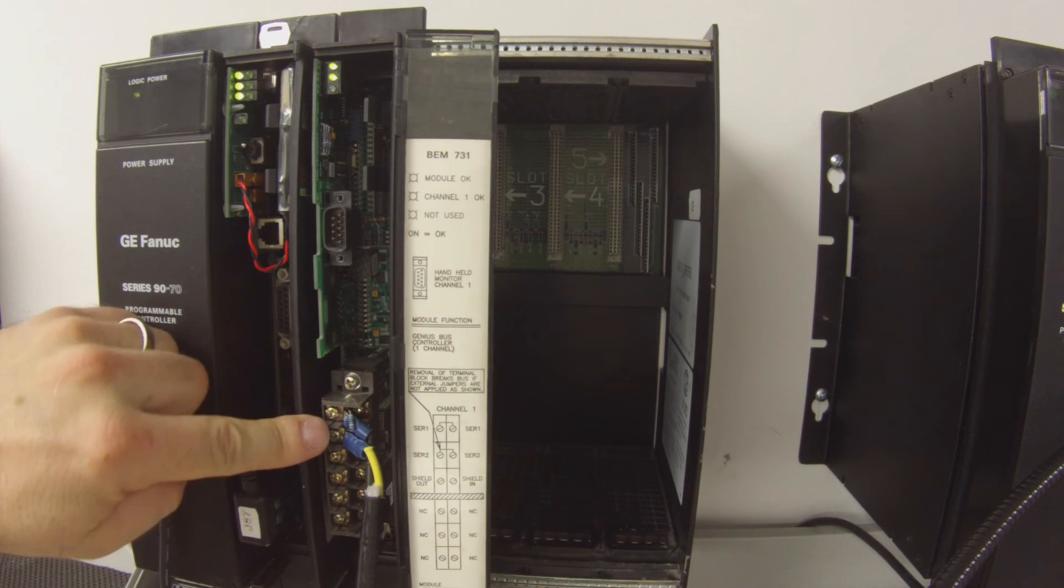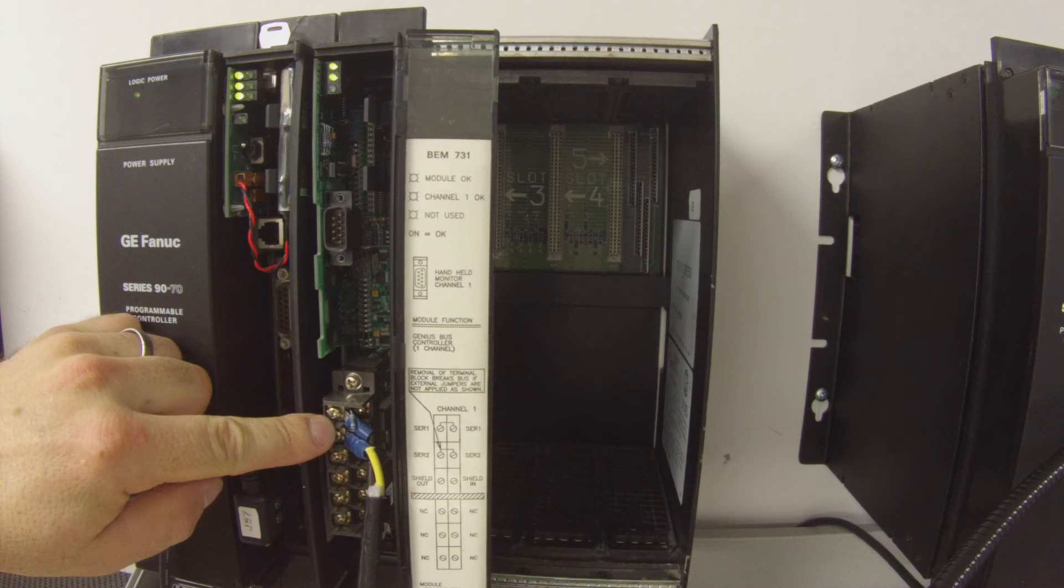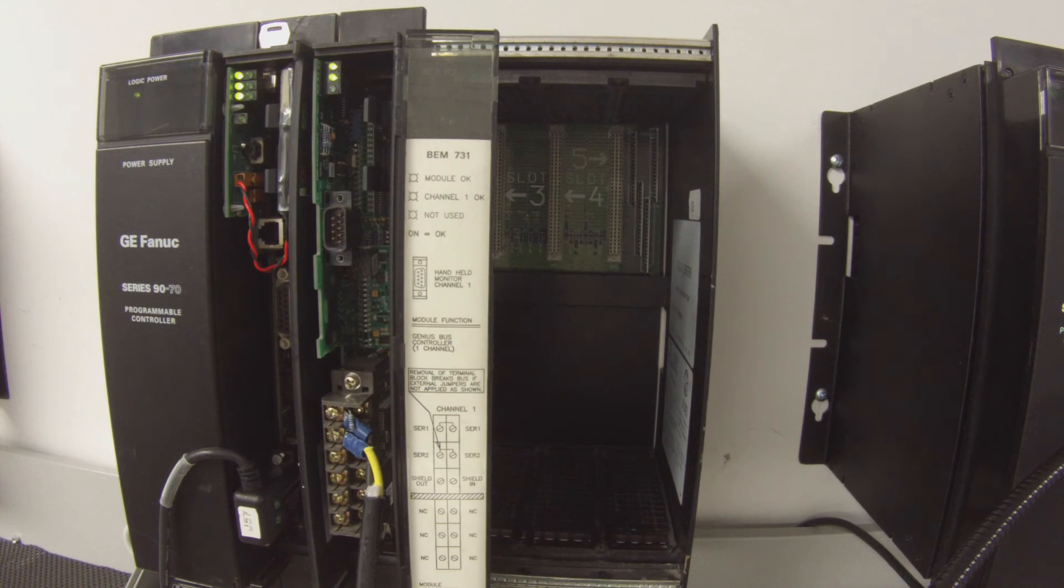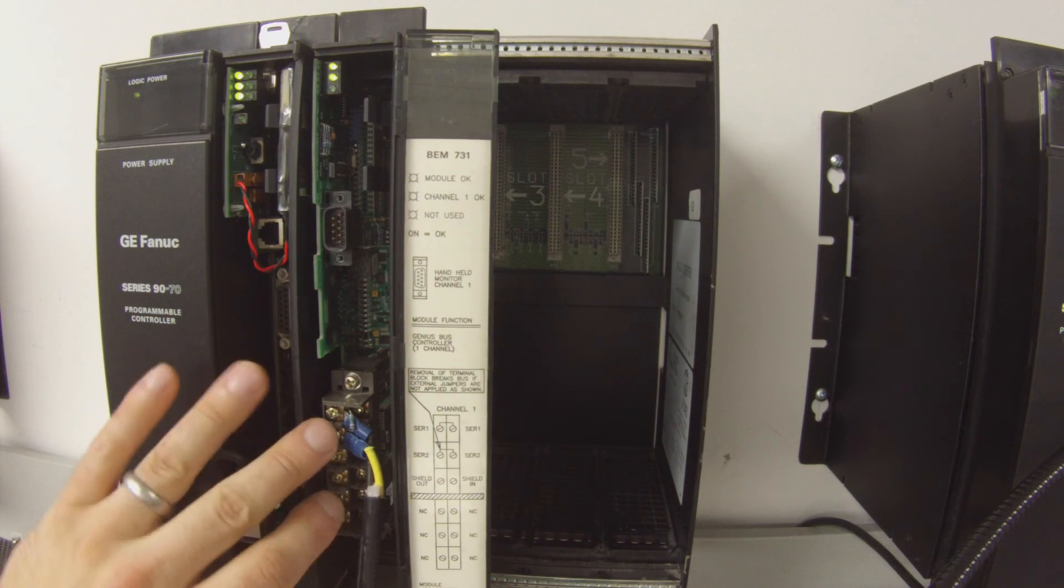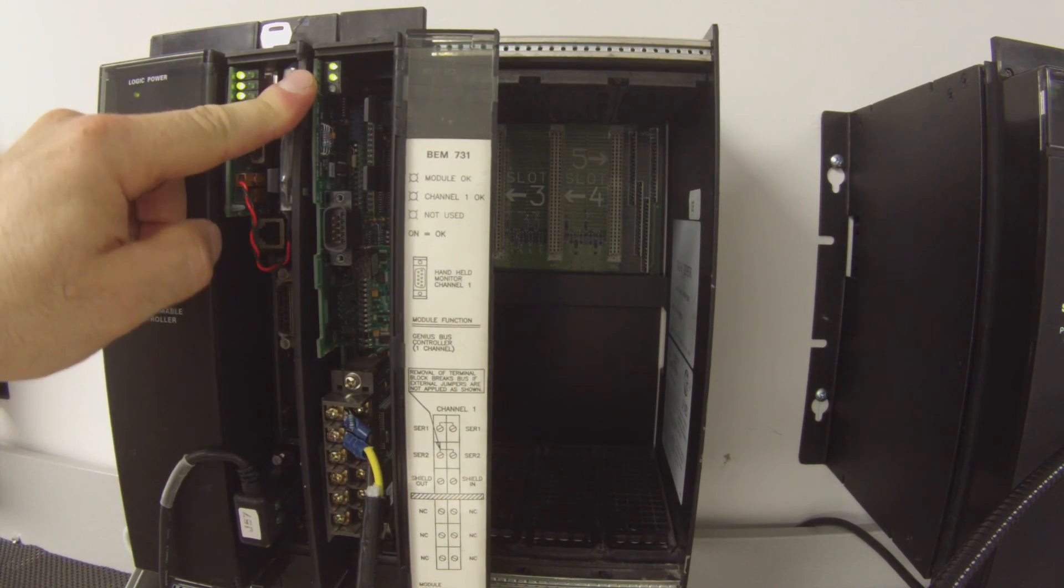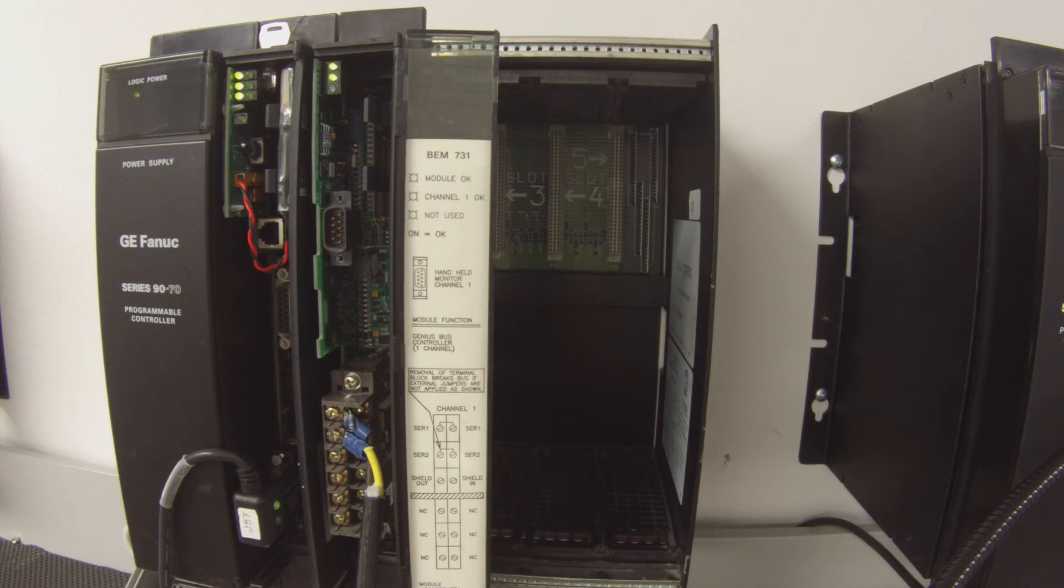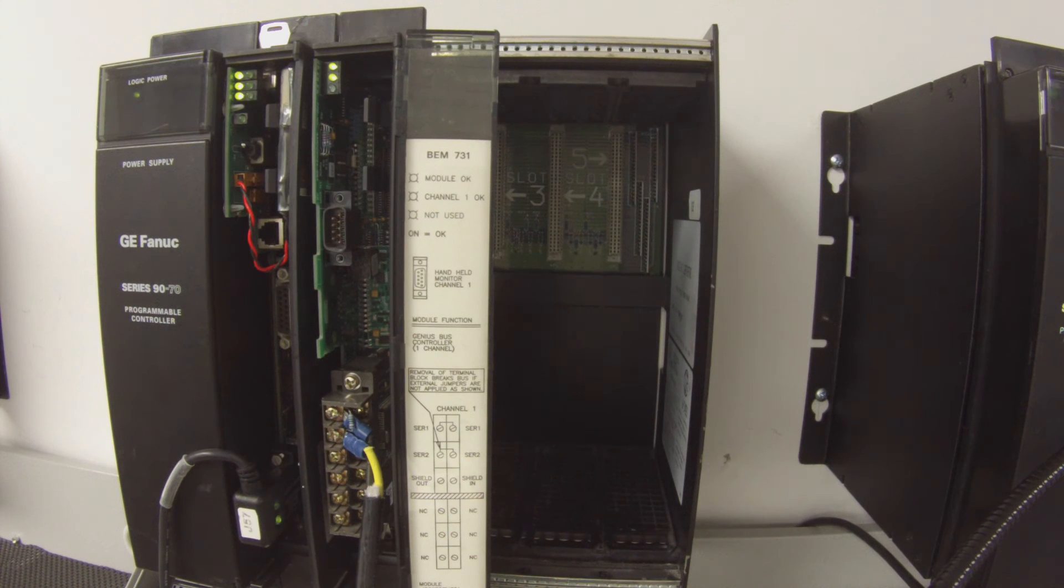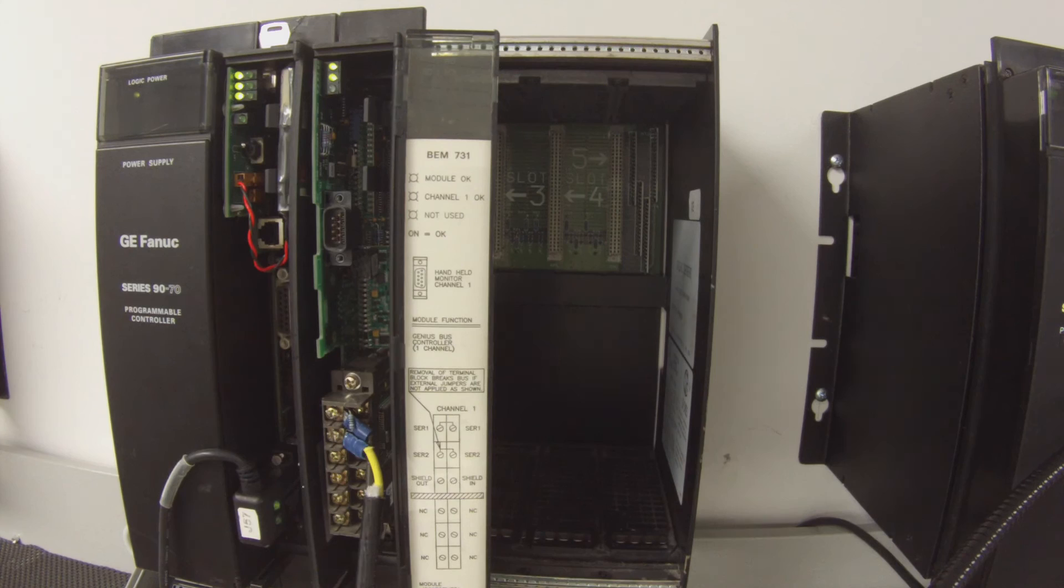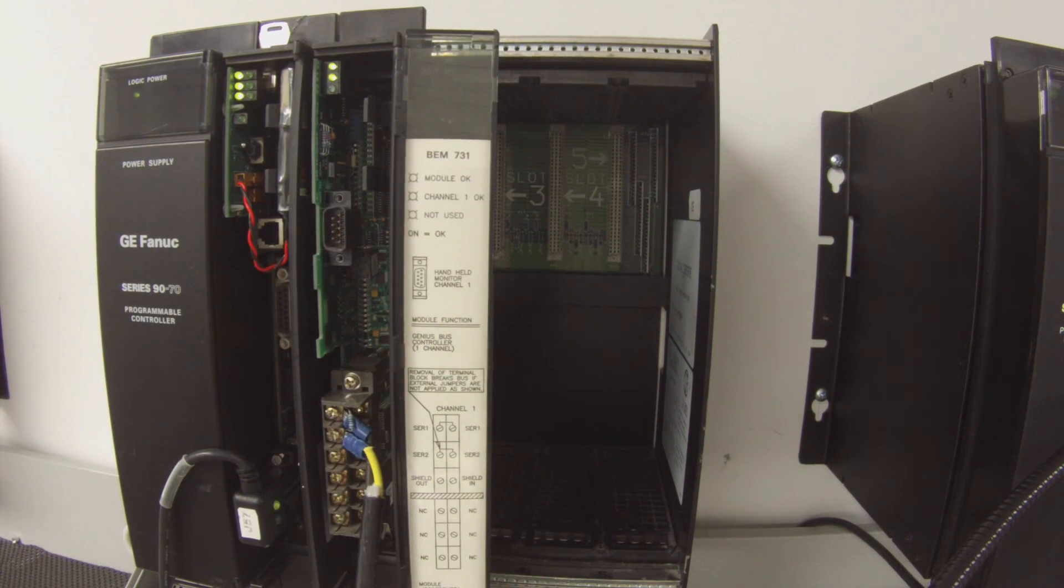Same thing, if channel 1 isn't working, and you have the configuration as serial bus address number 1 for your block, and the block is a working block, and you don't have an IO-enabled light, then this isn't working. So, there are times where these lights are working, and telling you you have a perfect device, but these aren't working. So, again, this is not an uncommon thing. We see it a lot. It's something that we can repair here. We offer exchange programs, keep in mind, new and remanufactured products, and we offer same-day shipping. So, if you have a problem with it, and you need one, please let us know, pdfsupply.com. Thank you.